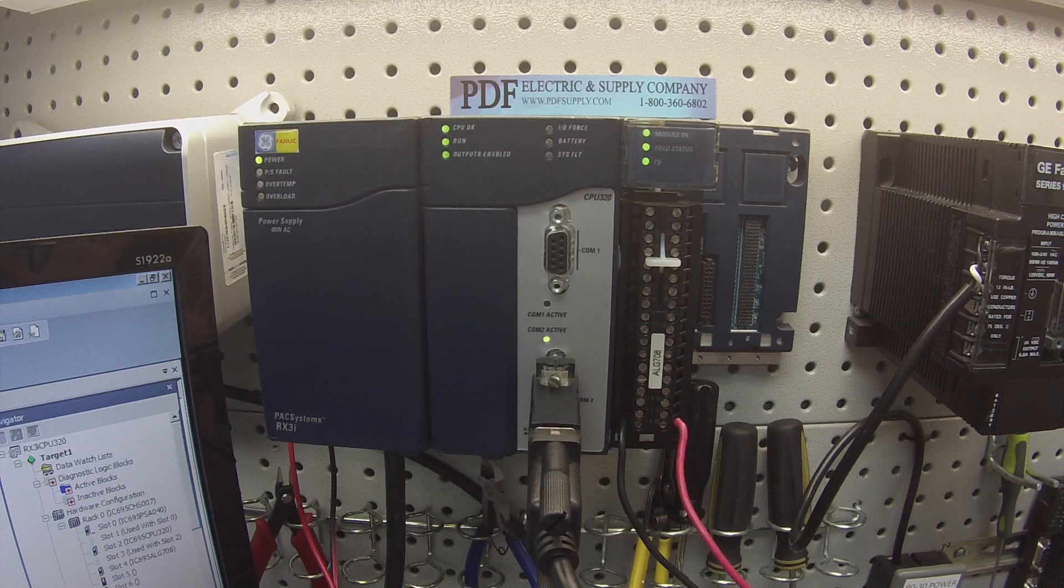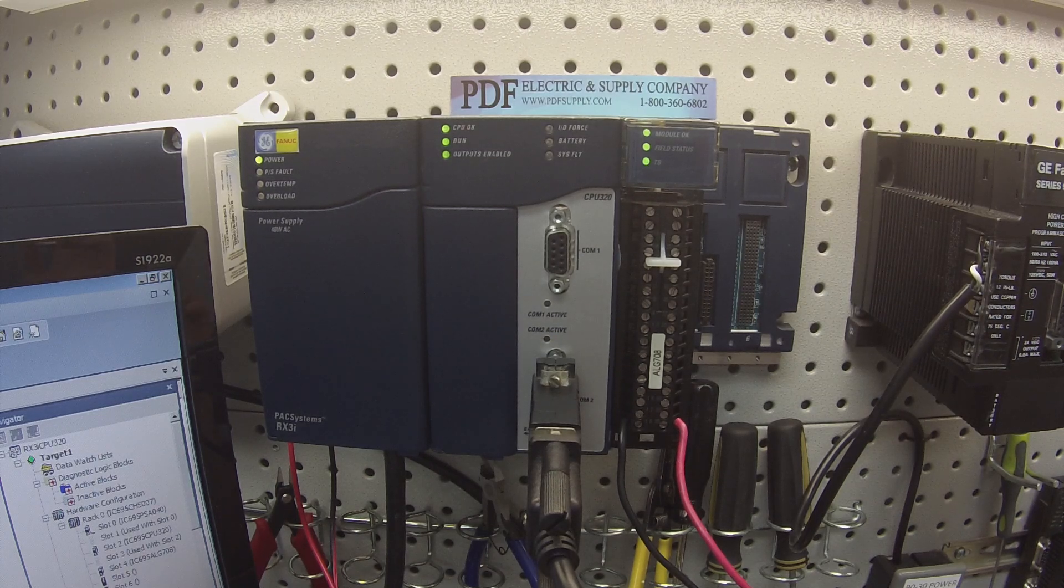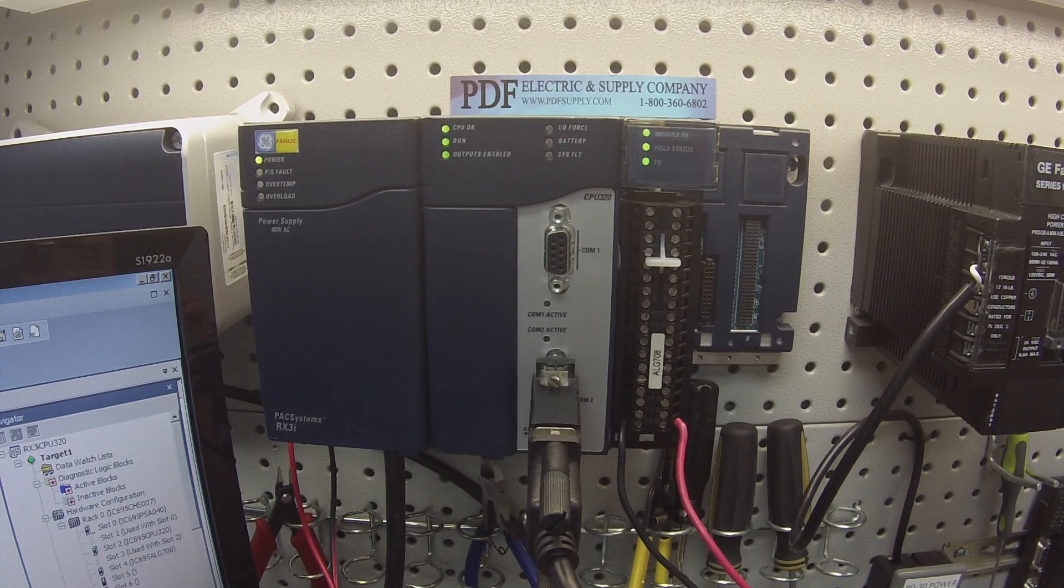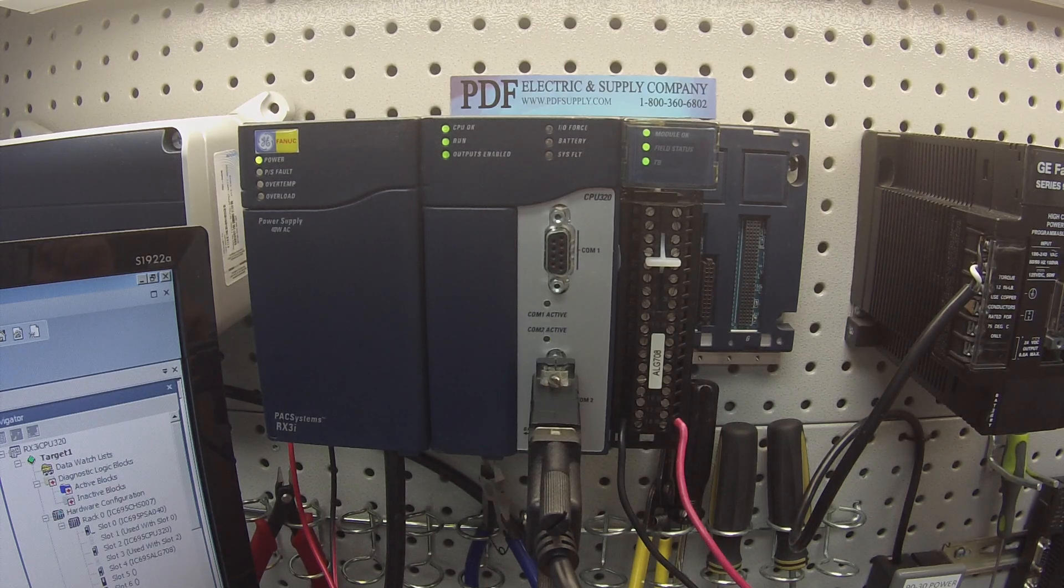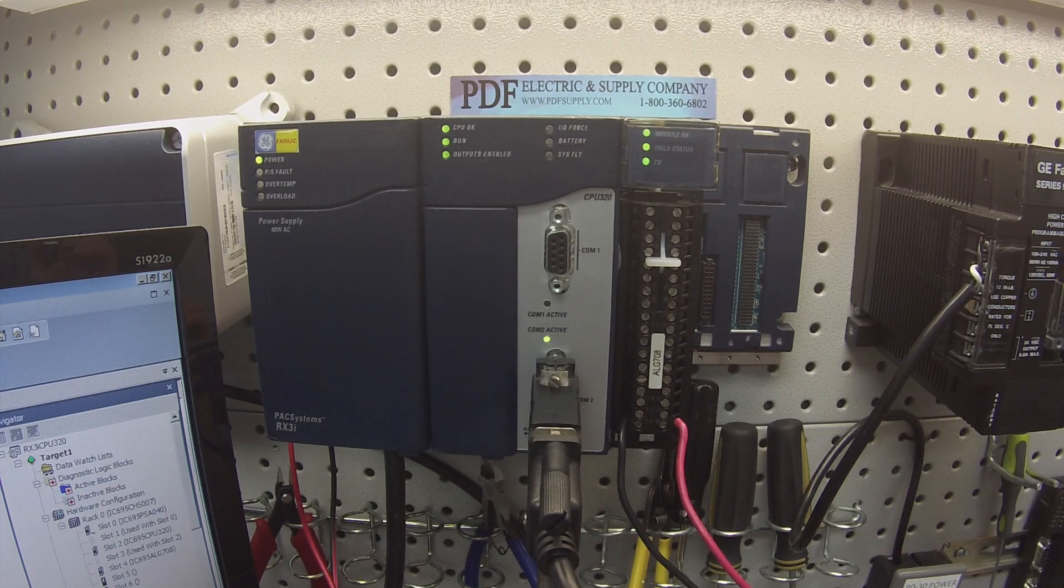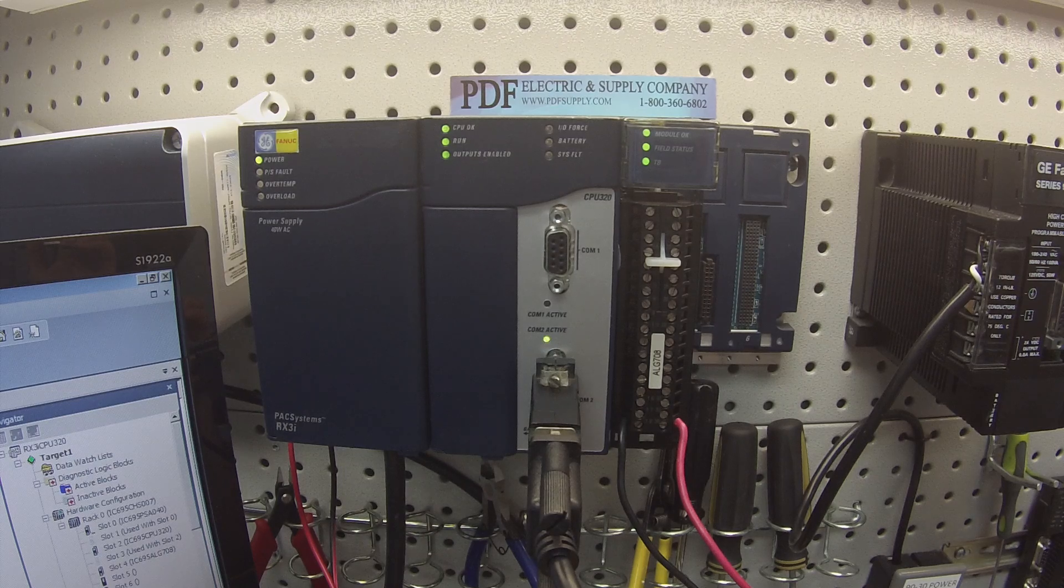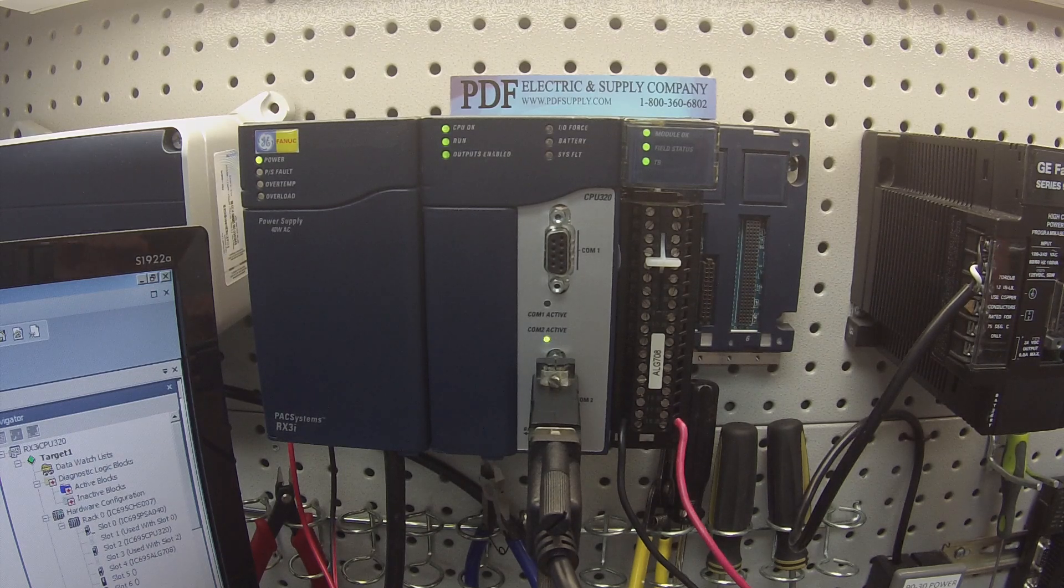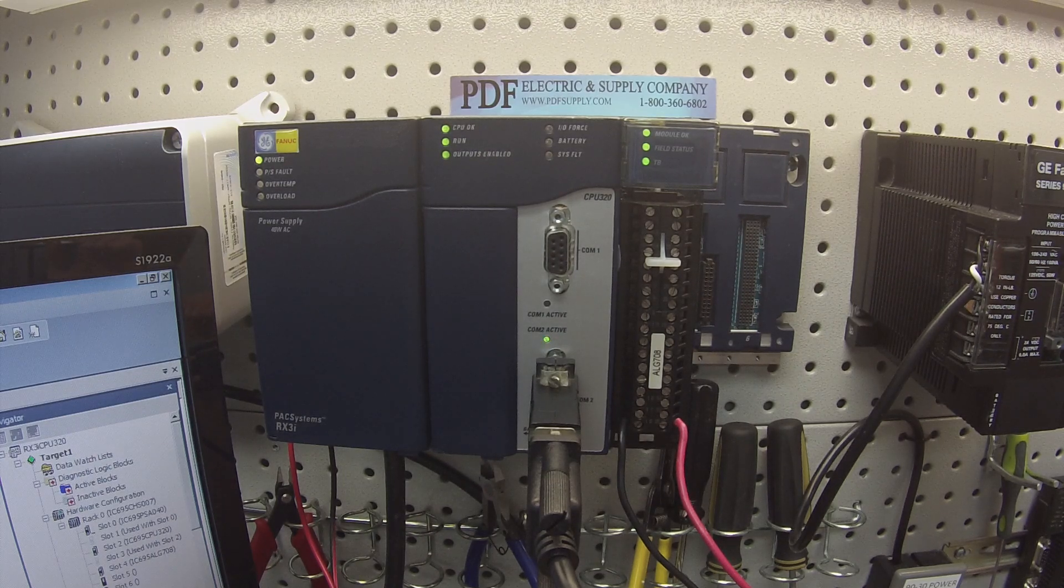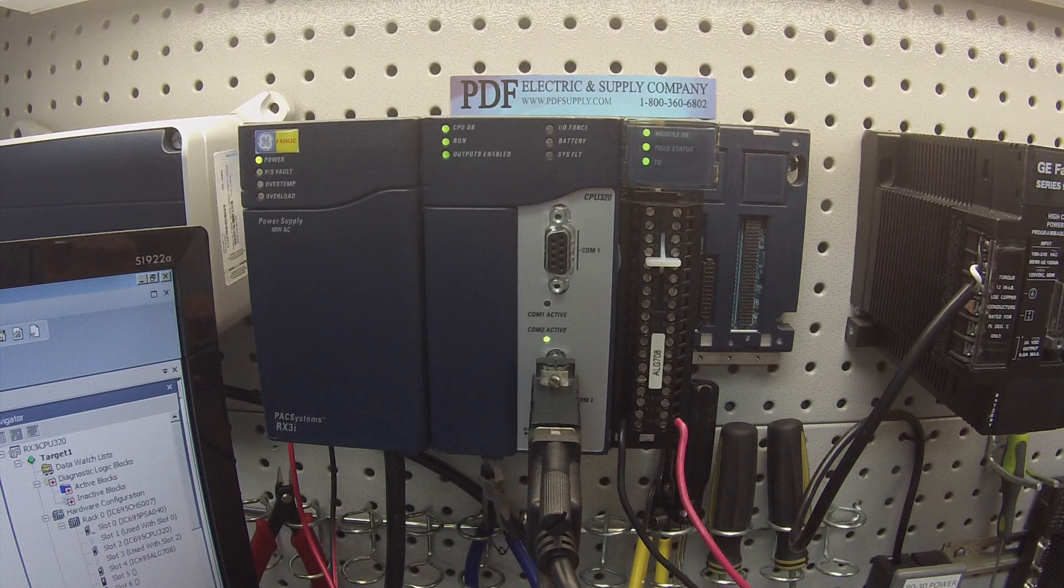More simply, if your field status, which is supposed to detect the 24 volt power supply, if that's not working, you have a problem. If your module OK light is not on, you've got a problem. By having a problem, I mean that the device is not going to be working. It needs repair. It needs a replacement.